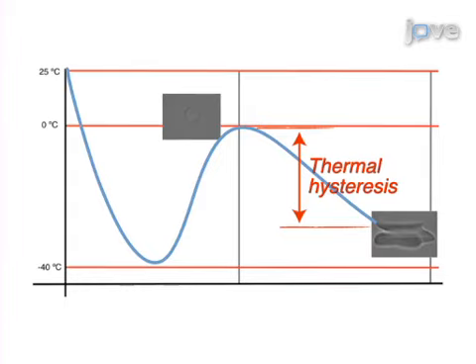The main advantage of the nanoliter osmometer that we developed over existing methods is that very long or very fast measurements can be made accurately and repetitively. This method can help answer key questions in the ice binding proteins field.